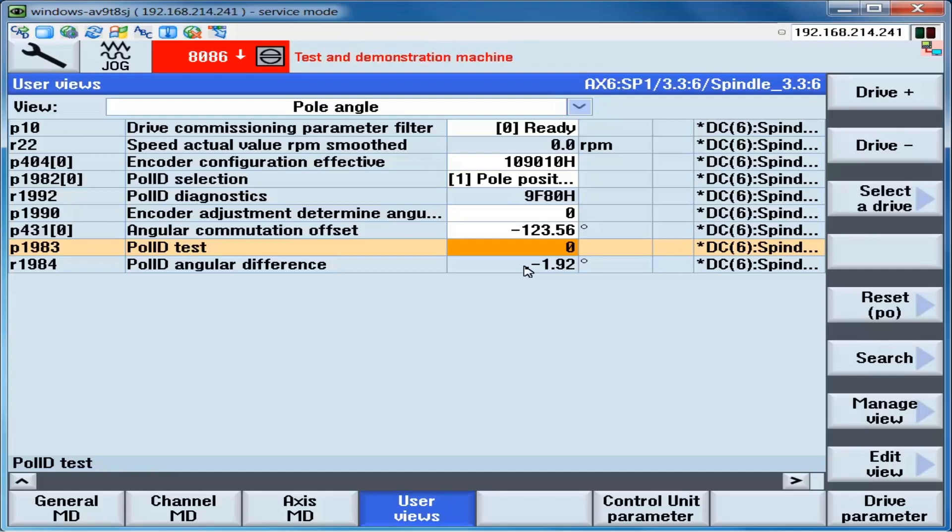Once we've tested about 10 different positions, we check the angular difference, biggest plus number versus the biggest minus number, and the difference between the two should be no more than 10 degrees. Peak to peak with the mean value of zero. When this is the case, the process and setup is complete.